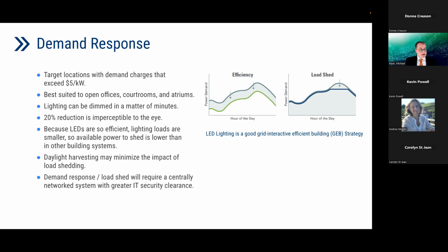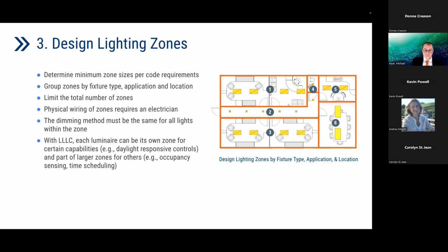We talked about, because LEDs are efficient though, some people are considering other loads, but I would encourage you not to overlook it. You also have something to think about where you have an interaction: if you're using those daylight controls and you're already dimming, you may not have as much load to shed through demand response. So something to think about as you're considering your priorities. The other thing to consider is because you're bringing this ADR signal, you do need to make sure you're dealing with the cyber mitigation and your IT security clearance, those types of things. Next slide.